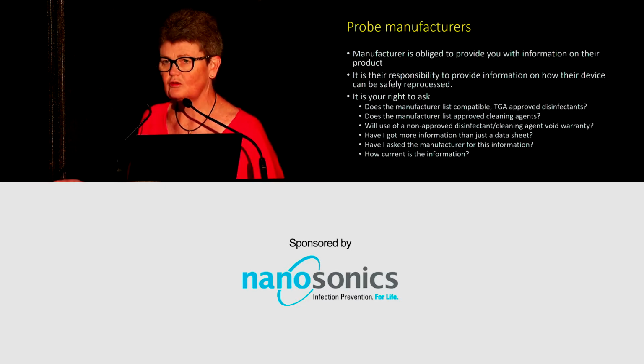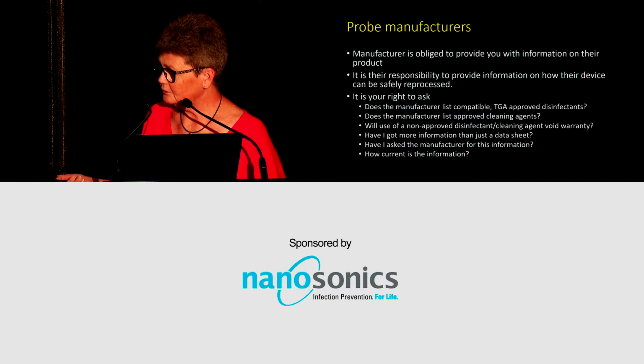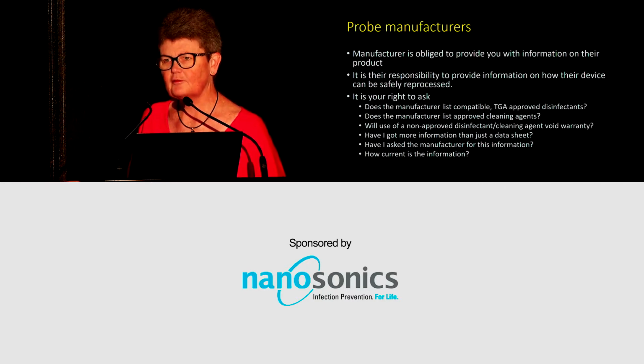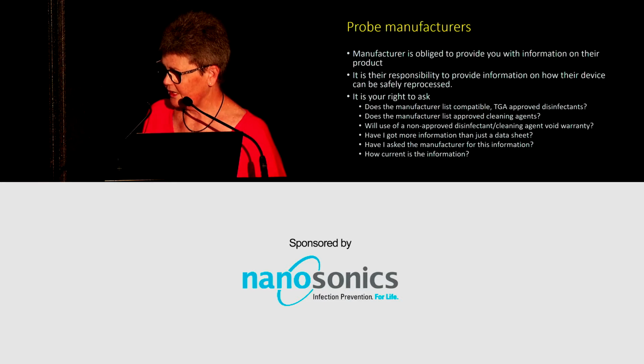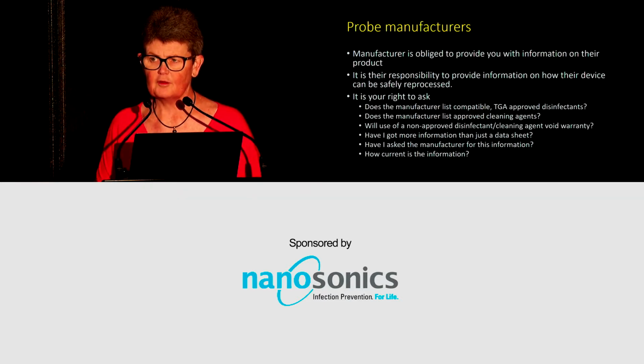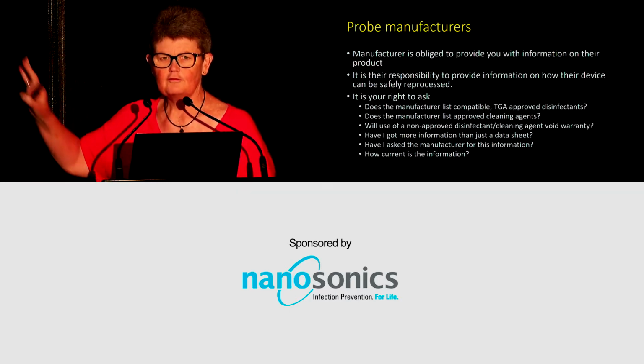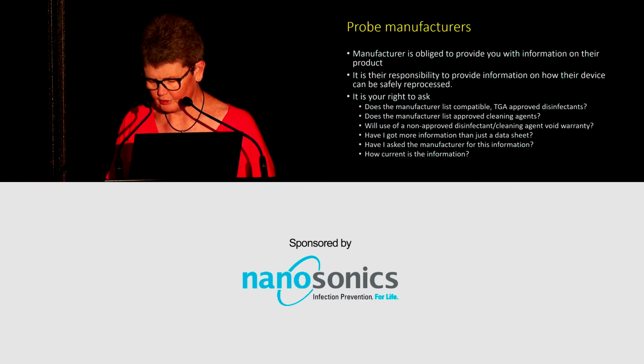You need to make sure what you're doing is compatible, that if you're using a disinfectant it's TGA approved. Are there compatibilities between the probe and the cleaning agents? Will the use of a non-approved disinfectant cleaning agent void the warranty on the particular device? And do they have any other information in addition to the data sheet or their marketing materials that they'll develop for you? And if they do, I hope you've asked them for that information, and then look at the currency of that information as well. And actually, that could go for any product that you're buying or purchasing, not just probe manufacturers.